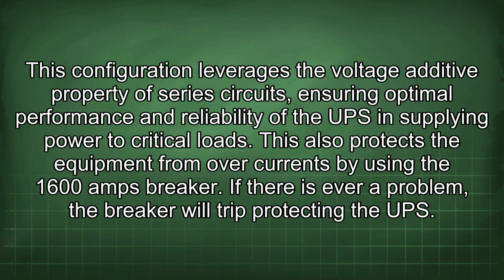This configuration leverages the voltage additive property of series circuits, ensuring optimal performance and reliability of the UPS in supplying power to critical loads. This also protects the equipment from overcurrents by using the 1600 amps breaker. If there is ever a problem, the breaker will trip, protecting the UPS.